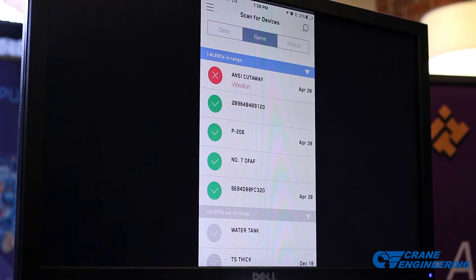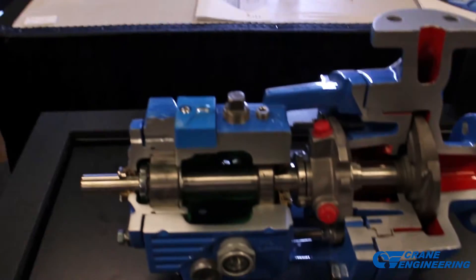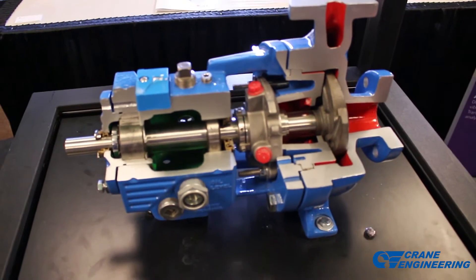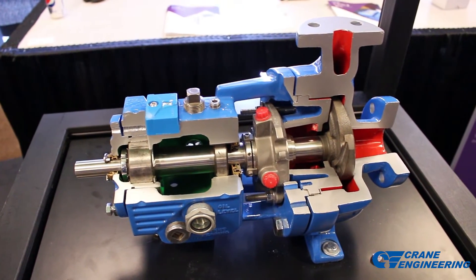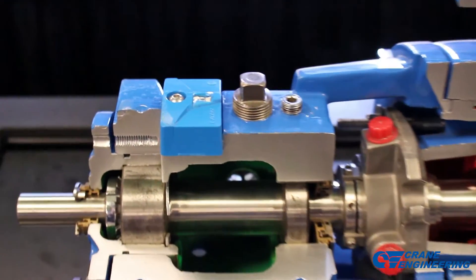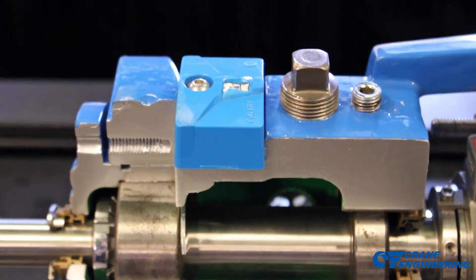The one on top there is what we've got on our ANSI cutaway and our vibration table here. The vibration table actually does vibrate — it's got a dial on the back with an adjustable frequency and amplitude. That red X is telling us that we've got a vibration problem with this particular machine.